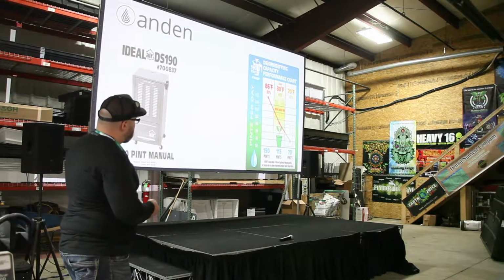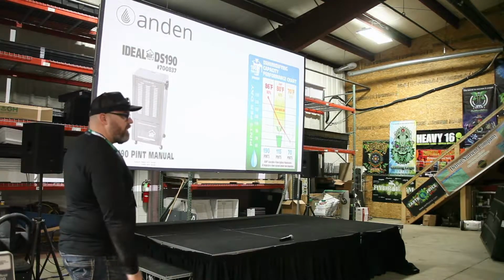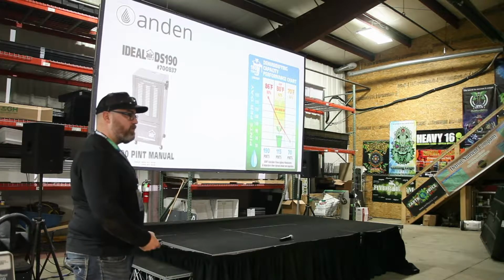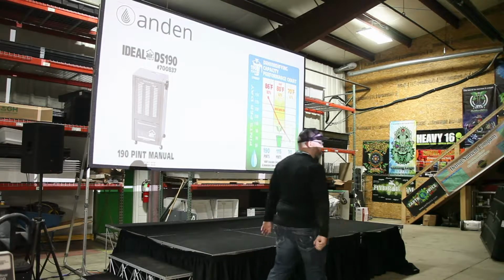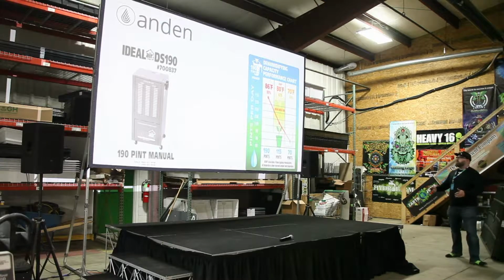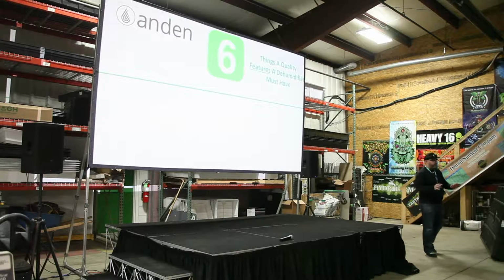So when we looked at these charts, we said, well, your goal is to build something that works really well right here. Because if you can do that, and you can combine that with a control that monitors it the right way, you can start to solve the biggest problem in the environment, which are those microclimates going out of control. Your room might think it's 60% relative humidity, but around your plant, it's 65. And that's something that you had to be able to change. So to do it, it's actually not that difficult.